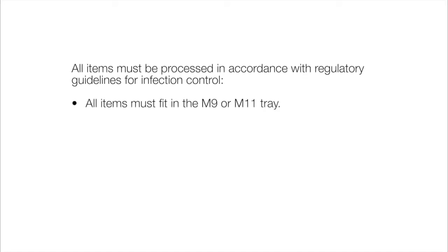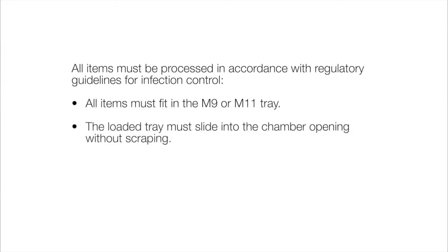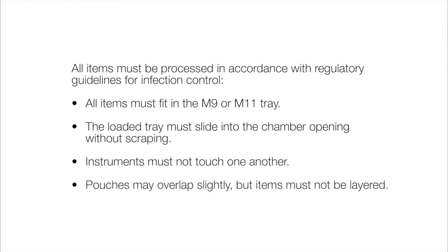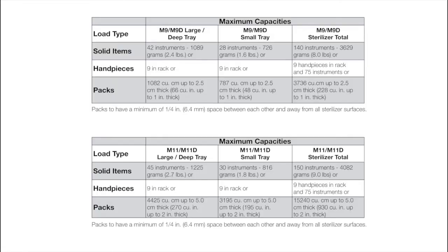All items must fit in the M9 or M11 tray. The loaded tray must slide into the chamber opening without scraping. Instruments must not touch one another. Pouches may overlap slightly, but items must not be layered. Refer to these charts in your installation and operations manual for maximum sterilization loads. If a load surpasses these limits, we recommend dividing the load and running multiple cycles.